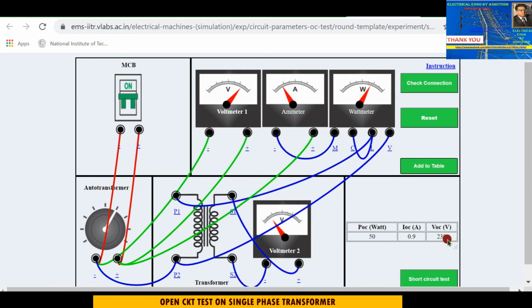The no load voltage is 230 volt, that is your rated voltage, because the open circuit test is conducted at rated voltage. So you have to apply single phase rated voltage of 230 volt, and this 230 volt is measured by this voltmeter. Then the no load current is 0.9 ampere, which is very, very small. You must have studied in your theory classes that no load current is very small during the no load test or open circuit test, and this is the core loss. You can see here, the wattmeter measured the core loss, 50 watt.